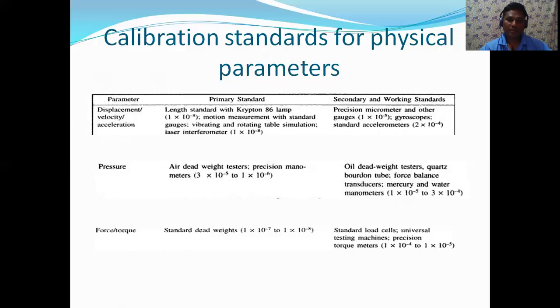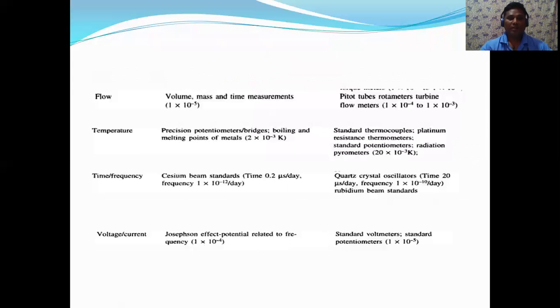The next parameter is pressure. The primary standard is the air dead weight tester, at 3 × 10^-5 to 1 × 10^-6. That is the range. The secondary and working standards are oil dead weight testers and mercury and water manometers, at 1 × 10^-5 to 3 × 10^-4. The next parameter is force or torque. The primary standard is dead weight, at 1 × 10^-7 to 1 × 10^-8. The secondary and working standard is the precision torque meter, at 1 × 10^-4 to 1 × 10^-5.